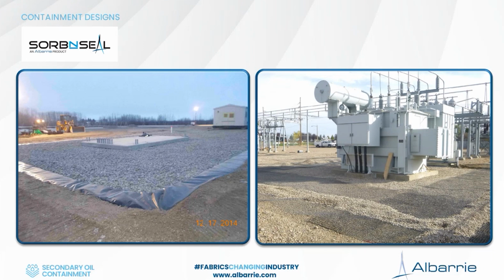The other thing to think about: if you have 4 or 5 transformers in a single containment, the containment area is big because it's encompassing all that equipment. If one were to fail, you'd potentially have a larger area to clean up. So that's something you have to balance - cost versus future state.